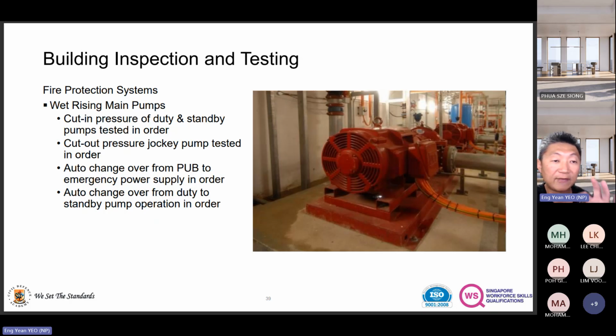As I mentioned to you, when we do that visual inspection, why I look at the jockey pump cutout is because that is the pressure the system was designed for: once the jockey pump has pushed the pressure to 180, it cuts off automatically without activating the alarm. So that 180 PSI, I will deem as the pressure the system is designed for. This is the pressure that we should maintain during standby mode for the sprinkler system.